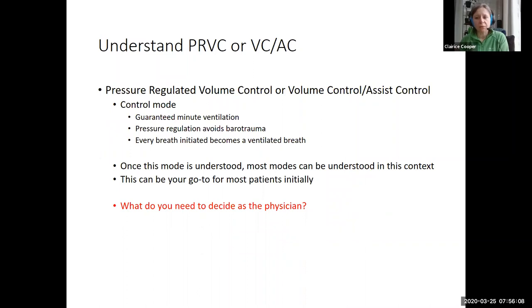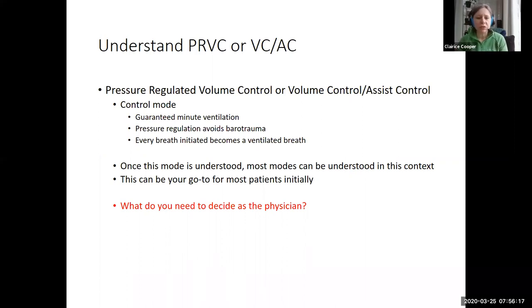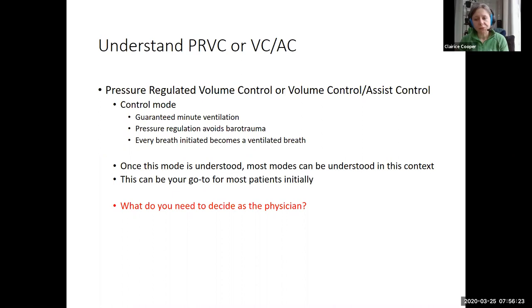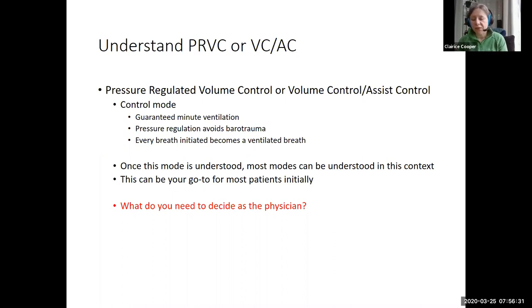Returning to what I was talking about — PRVC or VCAC, these are pressure regulated volume control or volume control assist control. Most people still call it PRVC. The new Dräger vents that we got at ECMC use VCAC. All the settings are the same; there are probably some slight internal differences that don't really matter to you. You can think of these for the most part as interchangeable.